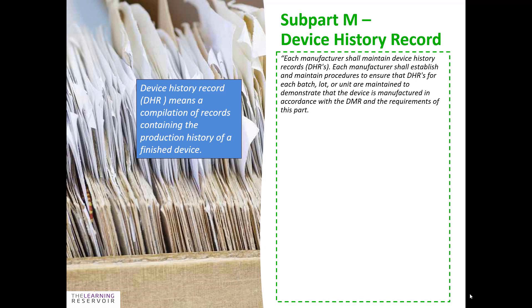In other words, your device history record comes after your device master record. Your device should have been manufactured in accordance with the procedures and specifications that are in your device master record, and out of that will come your evidence that this has occurred, and that will be found in your device history record.